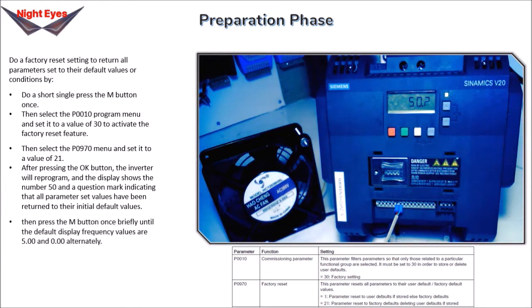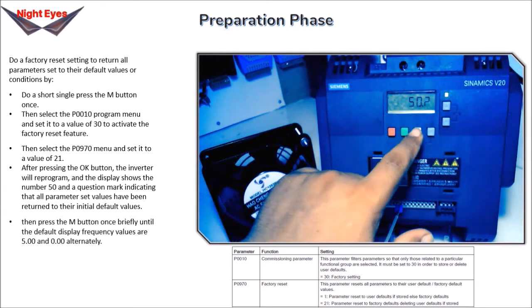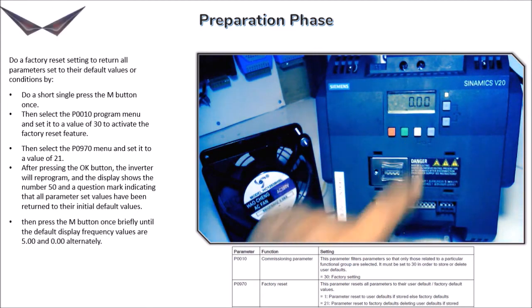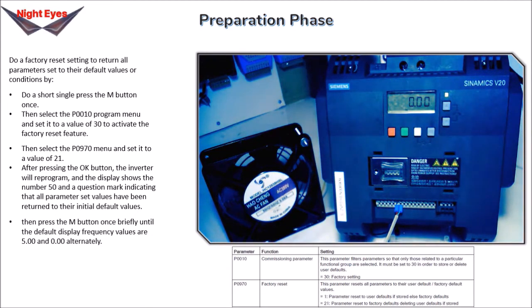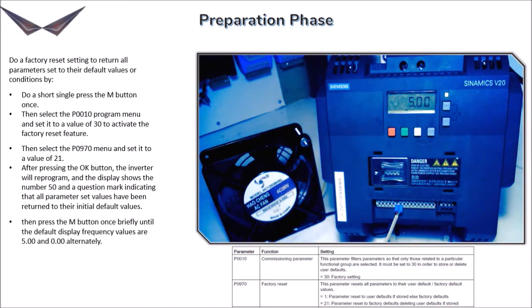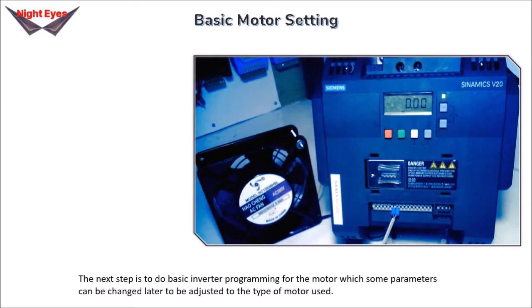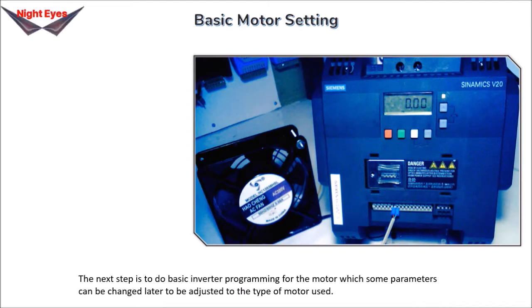Then press the M button once briefly until the default display alternates between frequency values of 5.00 and 0.00. The next step is to do basic inverter programming for the motor, where some parameters can be changed later to be adjusted to the type of motor used.